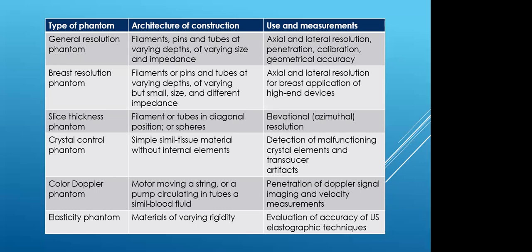And then for Doppler, there are specialized Doppler phantoms. And these are not really difficult, even in terms of setting up through a decent workshop, because it's a motor circulating a fluid at a known rate. Then you could, in different directions, do a scan, and as long as you get the same result, then you are fine. But you could also actually buy that. Then you also have phantoms for elasticity, which measure material rigidity.